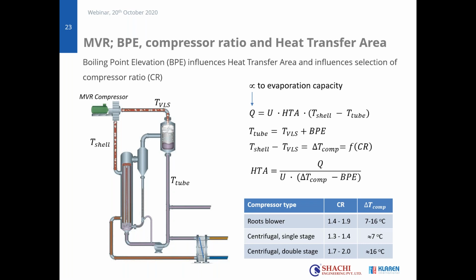dependent on the temperature rise that the compressor gives. And the temperature rise that the compressor gives is linked to the compressor ratio. It's also one of the questions asked. So the compressor ratio is really important because it will define the pressure rise over the compressor, the temperature rise over the compressor. So if you write that, then the difference between shell and VLS is in fact the delta T over the compressor. This is linked to the compressor ratio.